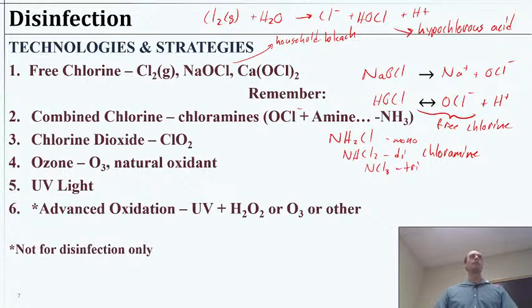You can smell it, you can feel it, it burns your eyes a little bit. That's actually a sign of lots of chloramine. That's not necessarily the free chlorine. It'll have a little bit of a smell for free chlorine, but not nearly that. Oh, there's so much chlorine here. And free chlorine actually doesn't sting your eyes very much. It's the chloramines. Now, how do they get there?